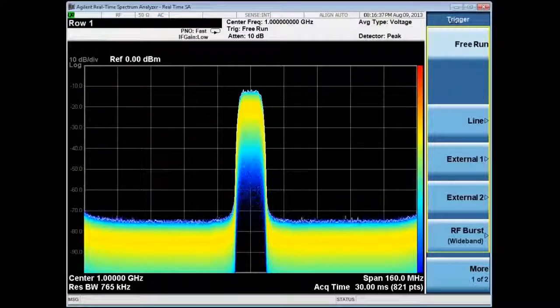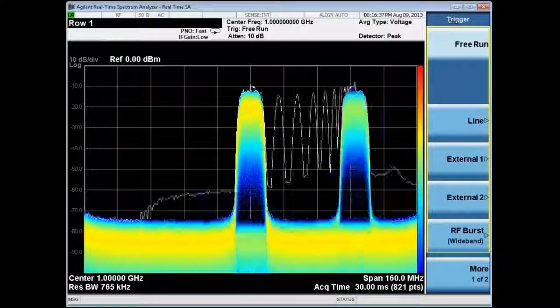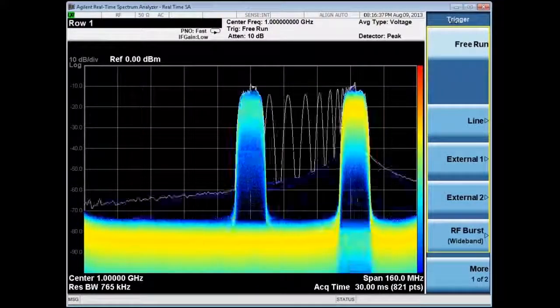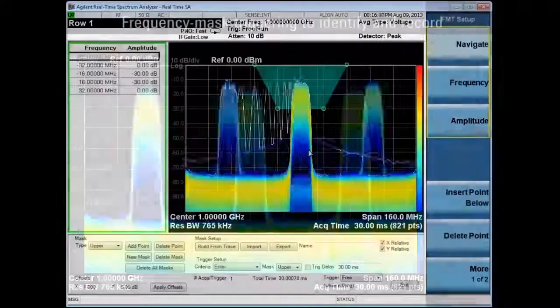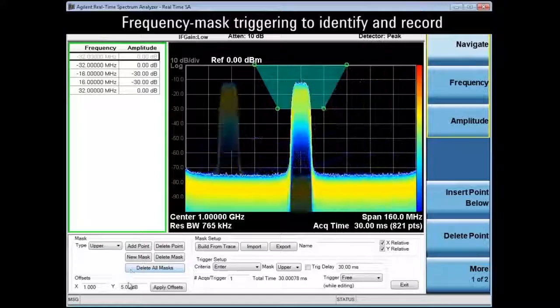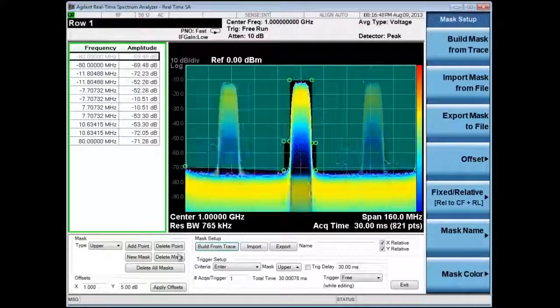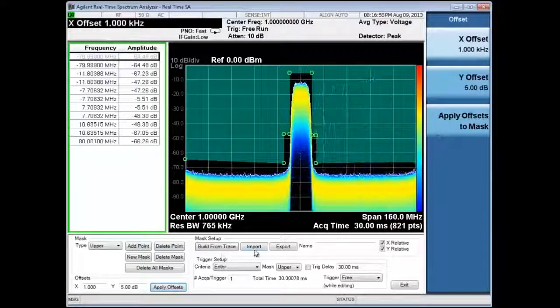If you wanted to understand as much as possible about a signal, a good approach would be to either use triggering or use a recording when triggering is not efficient. Most signal analyzers cannot record signals much greater than a few seconds at wider bandwidths. Fortunately, with the real-time MXA, we can use a frequency and amplitude selective trigger, which can be used to trigger measurements or recordings. This modulated carrier's unique hop sequence is longer than the analyzer's available memory, and hence the frequency mask trigger is needed to only record or measure the desired portion of the waveform.